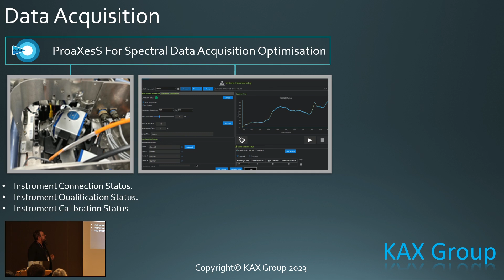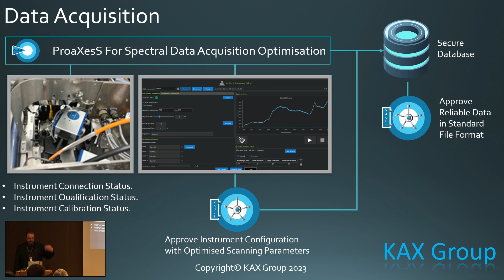Maintaining data quality and integrity in a PAT environment. Implementation of a Sentropat DLS probe into a process. Instrument connection status is monitored, instrument qualification status is monitored, instrument calibration status is monitored. Tick, we're ready to collect data. We optimize the parameters, in this case in the standard format. Save those parameters into a locked configuration that's been approved by somebody. Send it off to the database along with the data. Approve the data as reliable in a standard format. Generate reliable predictive models.